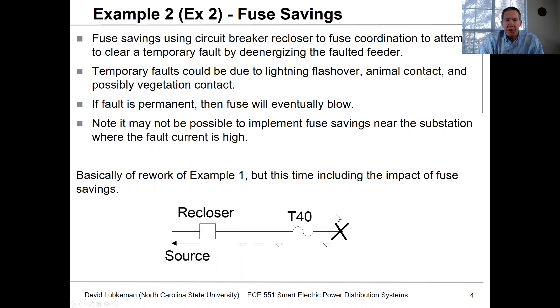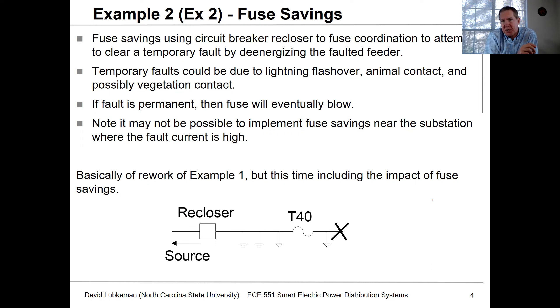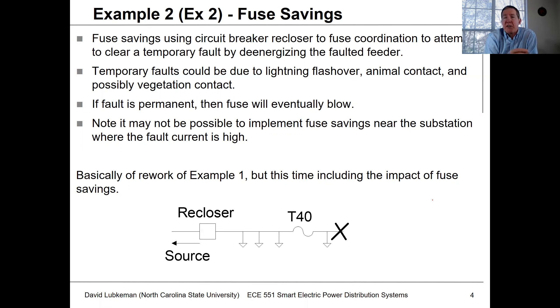Let's take a look at a fuse savings case, which is something that Mr. John Guida discussed in his lecture on distribution system protection. The reason we're so interested in this is that many faults on distribution circuits turn out to be temporary in nature. If I de-energize the circuit and re-energize it, that fault will go away — sometimes referred to as a self-healing fault.